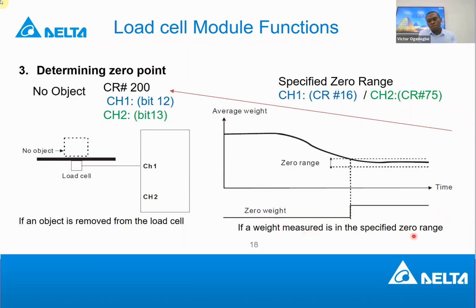So if the weight measured is in the specified 0 range, then you can track that, okay, what I'm measuring now is in the range that I specified as 0. That's for that. And then this is the third function. Sometimes you may not need this function if your application is not very sensitive. If it's just a simple application, you don't need all this. But there are some very advanced ones where you want to monitor every step of the weighing. Then we provide this function to help you to actualize that.